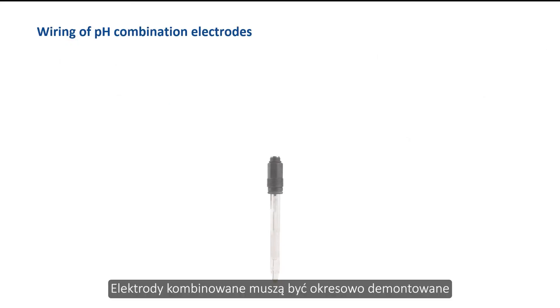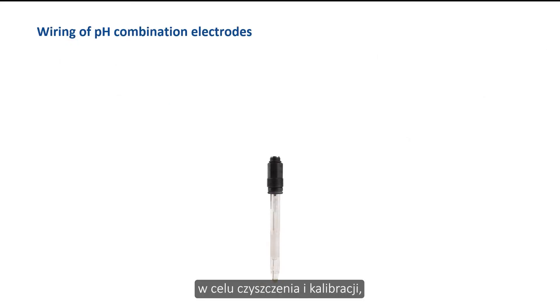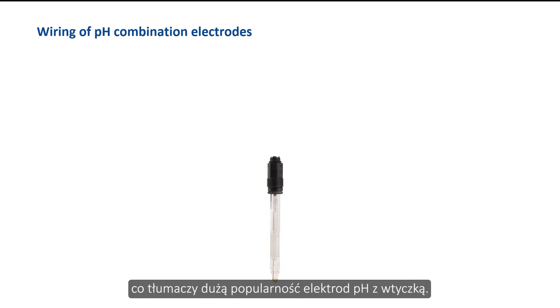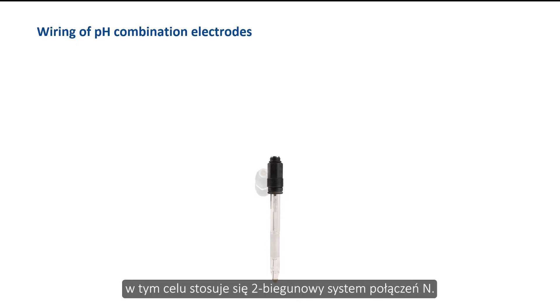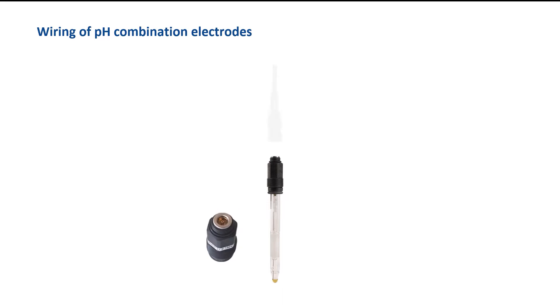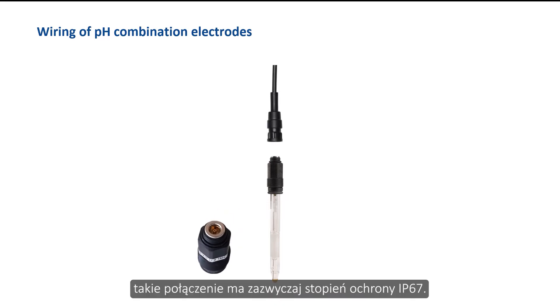Combination electrodes must be unscrewed from the fitting for cleaning and calibration, which explains the great popularity of pH combination electrodes with a connector plug. For combination electrodes without a temperature sensor, the potentials of the measuring system and the reference system must be transferred. The two-pole N connection system is used, and when mounted, this connection usually has protection class IP67.